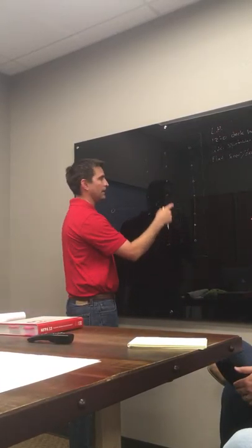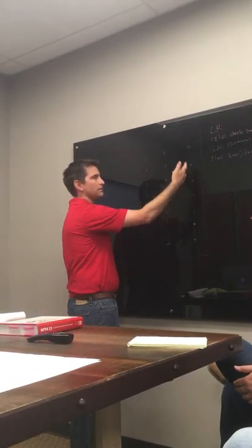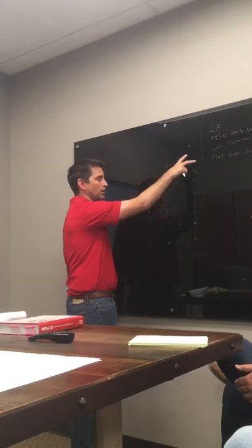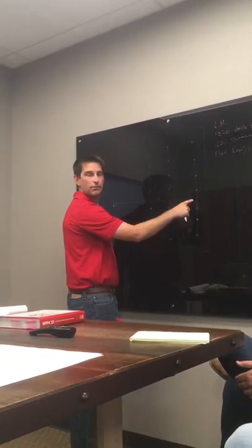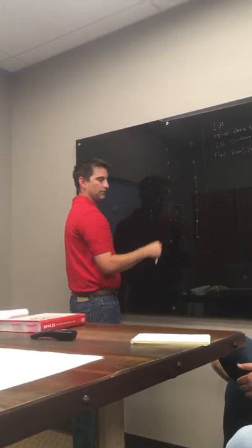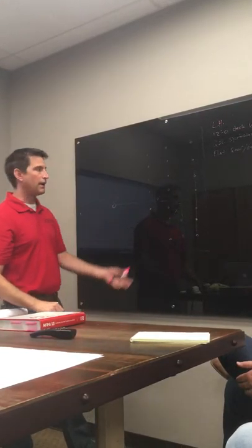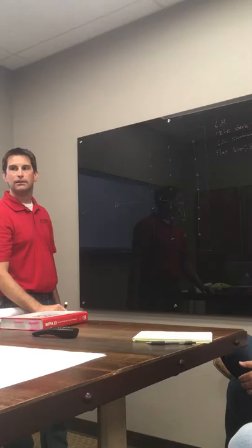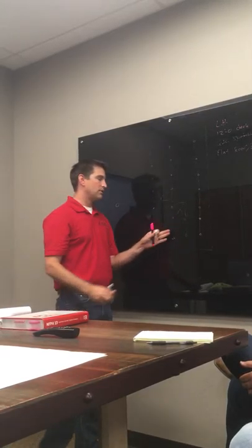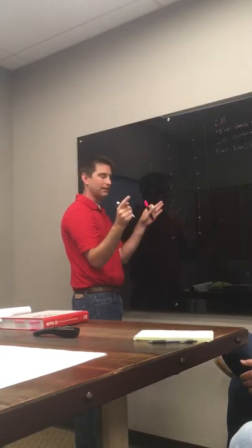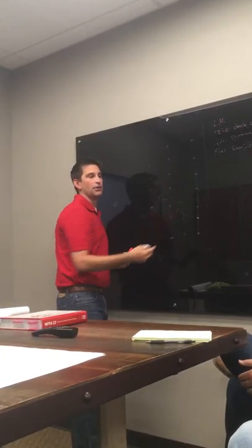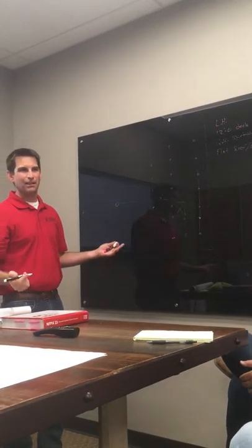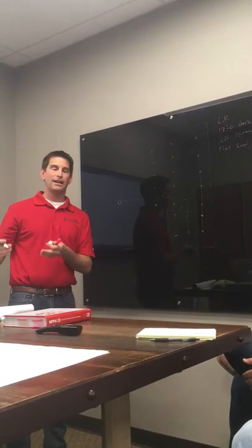Because now I didn't do anything different here. This is 4 sprinklers flowing, and this worked. And if I drew an area here, there's 3 on a branch line before it gets to a main. Right. 2, 3, it's going to work. So now I don't have to do 2 calcs, right? Versus what happens if I do this and I run this calc. Now to make this work, I might have to upsize that one piece of pipe. And now I've introduced a third pipe size into my system. And so now it's just one more thing I got to remember to order.